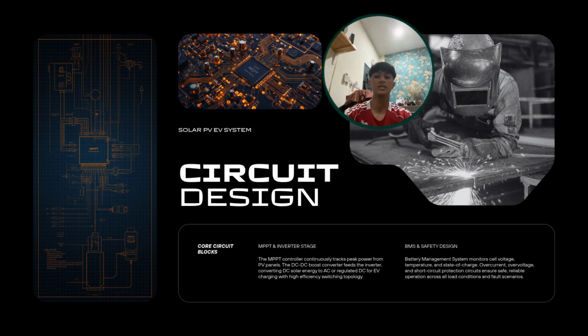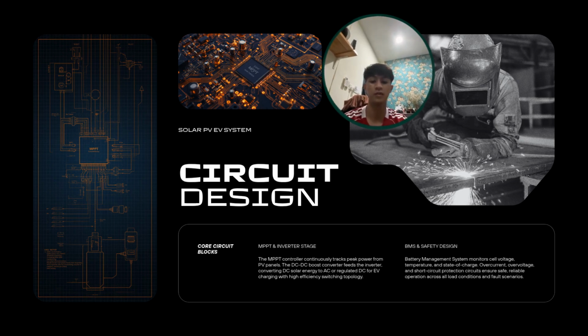Next, circuit design. This slide presents the circuit design of our proposed system. The solar PV panel supplies DC power, which is processed by the MPPT controller to maximize energy extraction. The DC-DC converter regulates the voltage before it is delivered to the inverter for AC conversion or directly to the EV charging circuit. The battery management system, or BMS, continuously monitors battery voltage, current, and temperature to ensure safe charging. Protection features such as overvoltage, overcurrent, and short circuit protection are also included to improve system reliability.